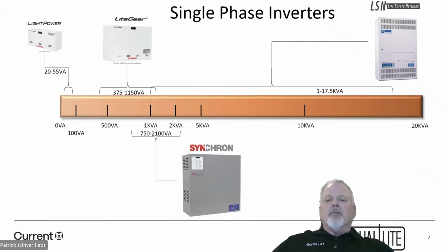With this unit, we typically will see it in multifamily, where the main priority is to just make sure we light our path of egress. There's not a lot of other things that we need to have on here. There's only 4 breakers available on that unit. So again, please keep that in mind. If you want more options, then I would suggest going to the Synchron.